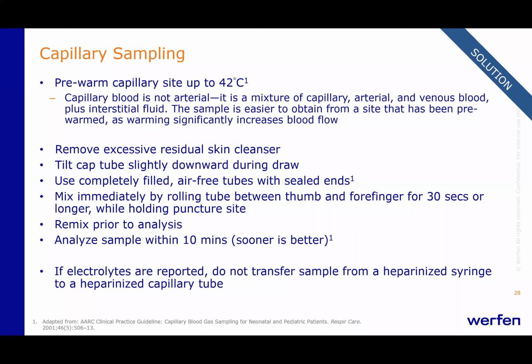Remove excessive residual skin cleanser, as mentioned. Tilt the capillary tube slightly downward during the draw. This helps gravity and capillary action fill the tube. Use completely filled, air-free tubes with sealed ends. Mix immediately, and again, this is extremely important. Do not set that tube down. Once it's capped, mix it by rolling the tube. The heparin is embedded in the inner surface of the capillary tube, and by rolling that tube, it mixes the heparin with the sample and will greatly reduce microclot formation. Remix prior to analysis and analyze the sample within 10 minutes, and sooner is even better.